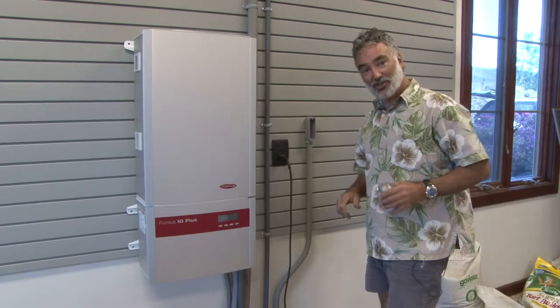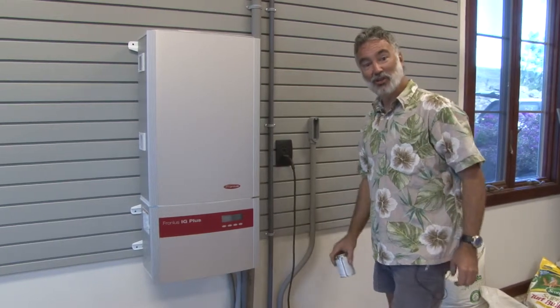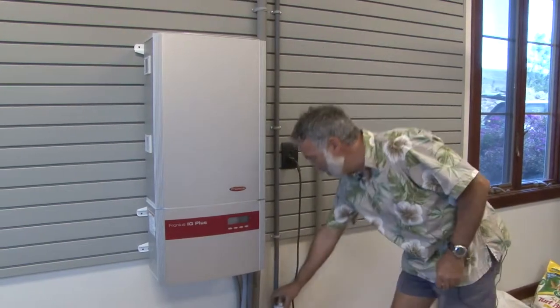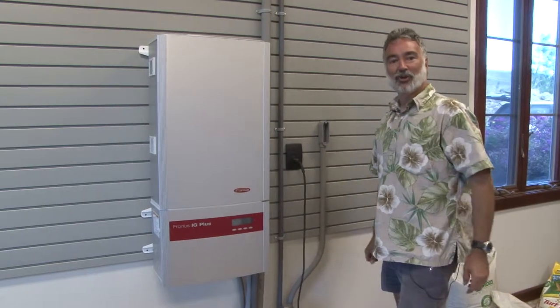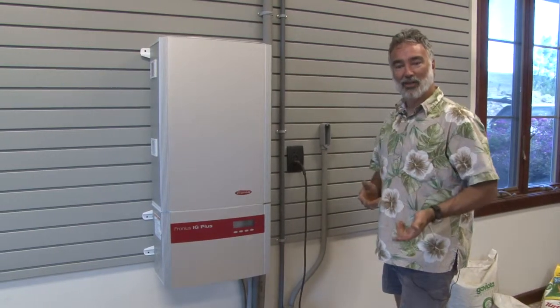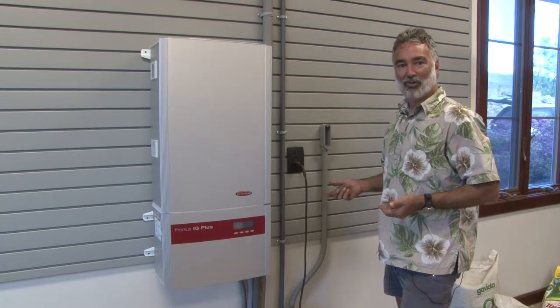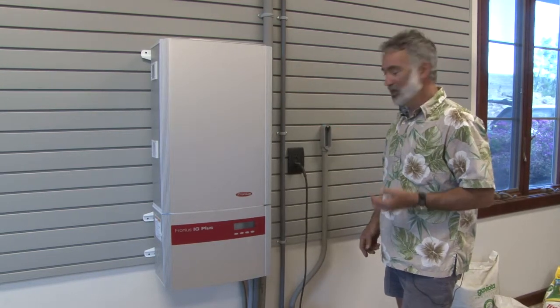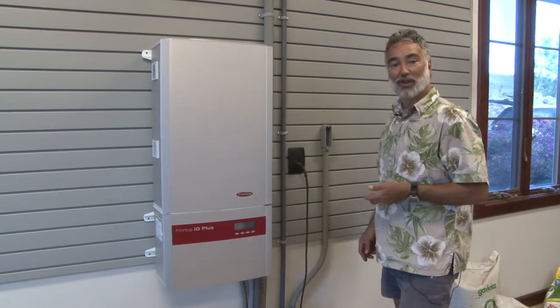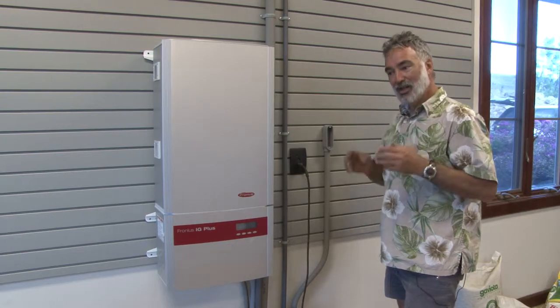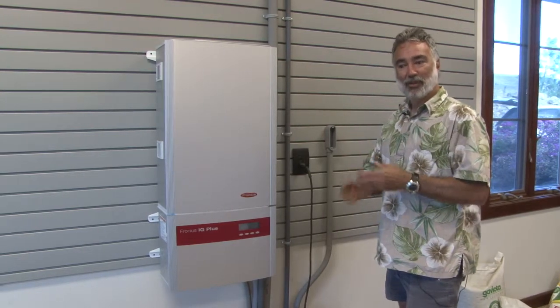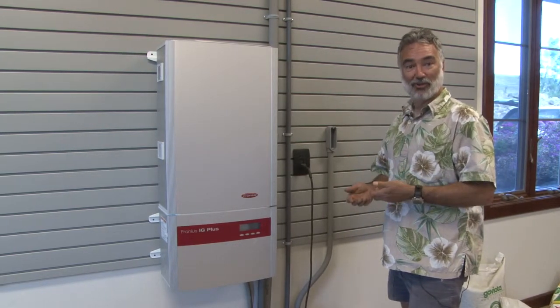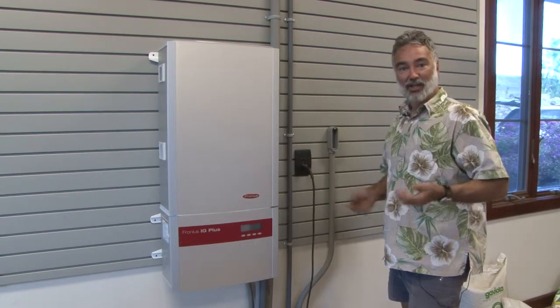We're pulling the MidNite Solar 600 volt custom 90 degrees C rated USE-2 jacketed Cat 5 cable, which is what you need for connecting the Birdhouse to the combiner box. It allows you to run it across a rooftop where it's exposed, and also put it into the combiner box with the high voltage PV wiring, because it carries the same 600 volt 90 degrees C rating as that cabling.